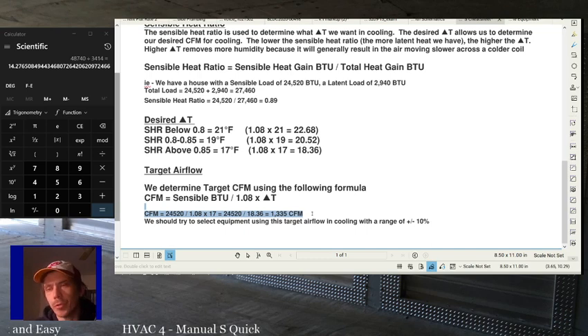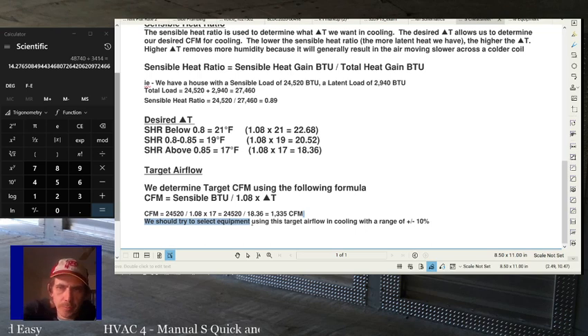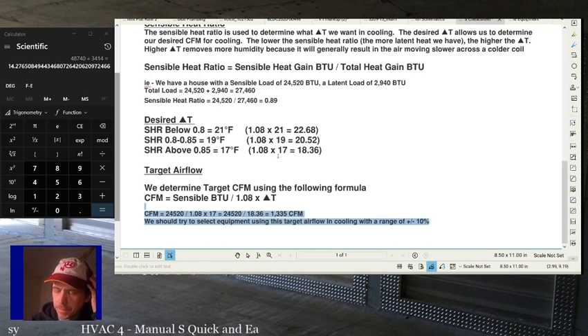So this is why it's important to know Manual S, because the load isn't what you think it is. The equipment doesn't put out what you think it does. And there are many things that can factor into what the actual BTU output of a piece of equipment is, and so on and so forth. So if you understand these rules and have done a few load calcs, you'll start to see that 3-ton ain't 3-ton, and where you want this changes a lot. So it's interesting once you get to know it. It's hard to do it until you've done a few real life examples. It's hard to really picture what I'm talking about.